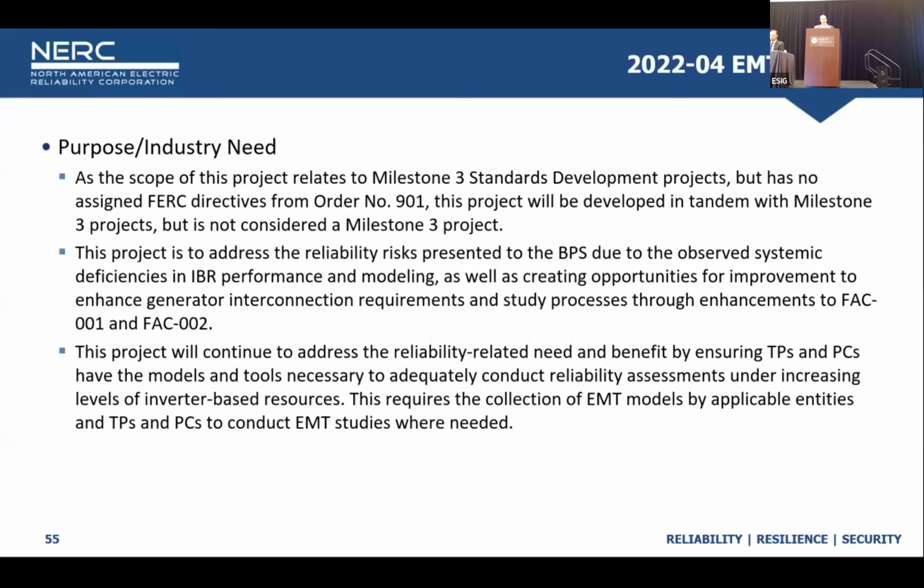We're looking at creating opportunities to enhance the generator interconnection requirements and study processes through enhancements to FAC-001 and FAC-002. This project is going to continue to address the reliability needs and benefits by ensuring the TPs and PCs have the models and tools necessary to adequately do these reliability assessments under increasing levels of IBRs. I think we all recognize that this is going to require a good collection of EMT models by all applicable entities and TPs and PCs to conduct the studies where needed. I want everyone to look at that sentence: EMT studies where needed. Okay, we're not looking to say everywhere. It's very much applied to where it's required.